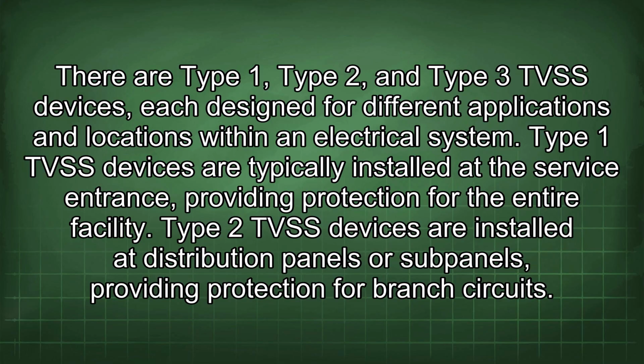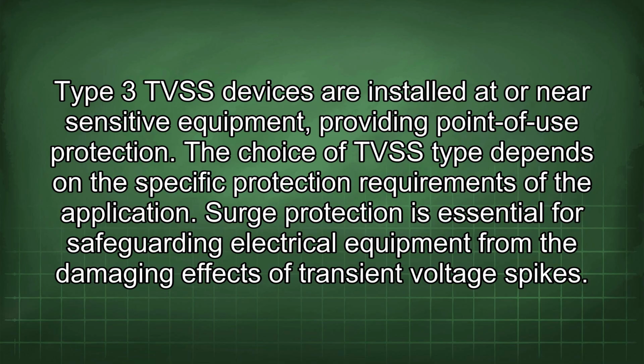Type 2 TVSS devices are installed at distribution panels or subpanels, providing protection for branch circuits. Type 3 TVSS devices are installed at or near sensitive equipment, providing point-of-use protection. The choice of TVSS type depends on the specific protection requirements of the application. Surge protection is essential for safeguarding electrical equipment from the damaging effects of transient voltage spikes.